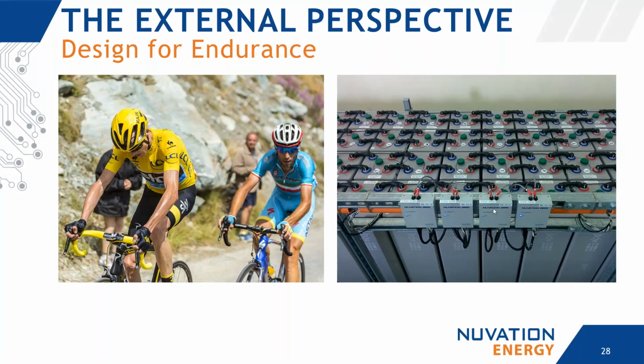What I've got here in the photo on the right is actually an example of a solar plus storage project we helped out with on an island. These are massive cells. They're, I think, 1,000 amp hour, if I recall correctly. And if you look at the connections between these, there's actually no bus bar. These are almost like little segments of booster cable pulling everything together. So you are not going to be pushing 1,000 plus amps through these interconnects.